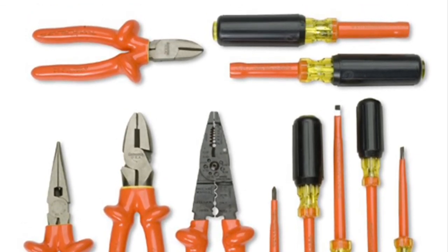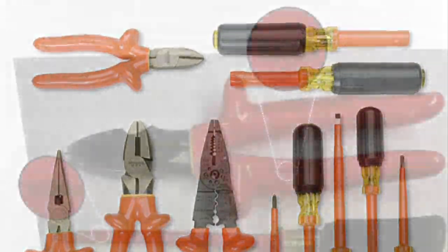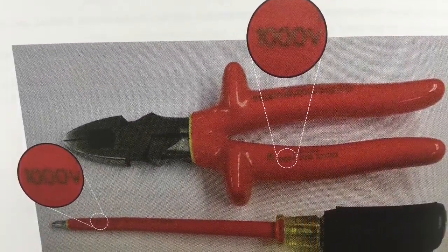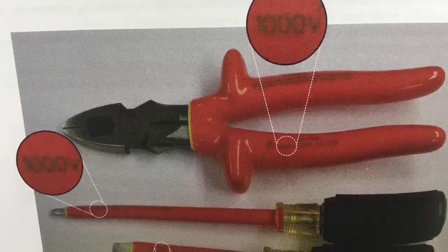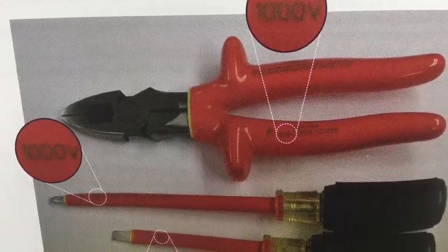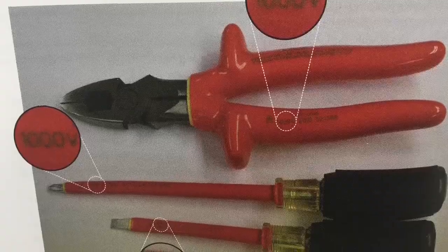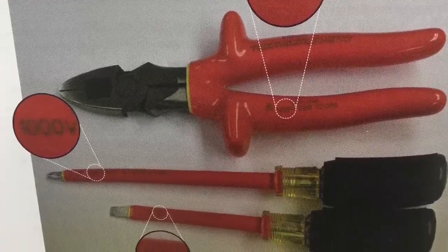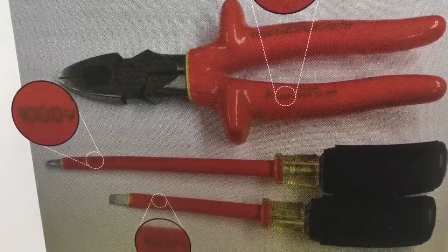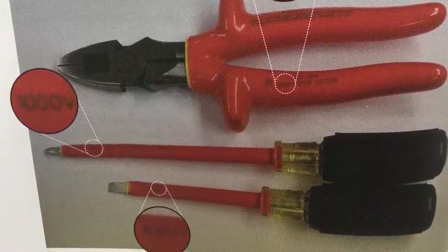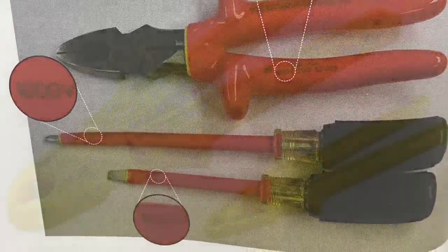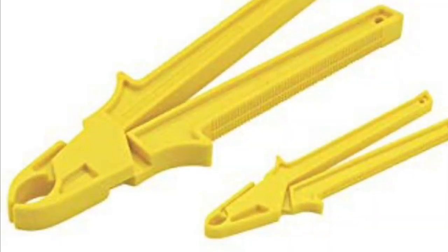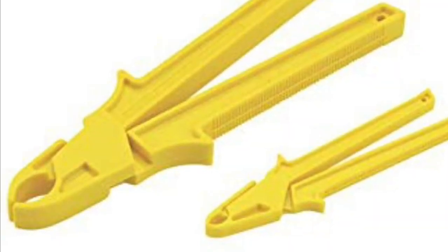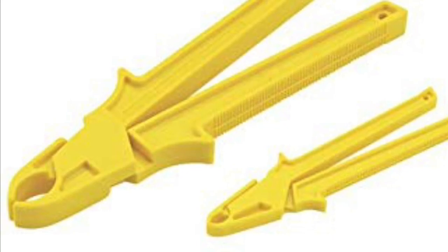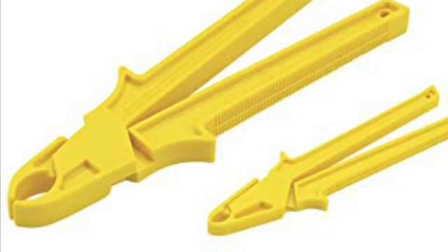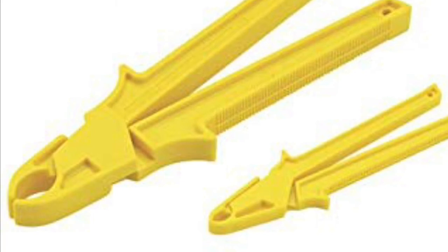For example, a damaged tip on a screwdriver. The term insulated means that the tool's manufacturer has assigned a voltage rating to the insulating material. Only tools with a defined voltage rating are considered to be insulated. It is important for employees to look at the markings on the tool before using it. Tools with unmarked rubber grips and plastic handles must not be used in lieu of a properly rated tool. Fuse or fuse holder handling equipment insulated for the circuit voltage shall be used to remove or install a fuse if the fuse terminals are energized. Replacing fuses live is energized work and, as such, must be justified.